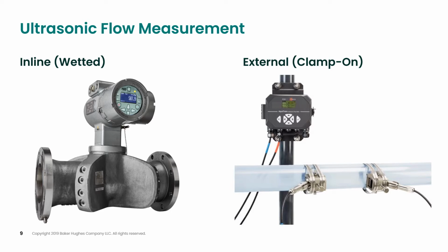With an external or clamp-on system, the transducers are installed on the outside of the pipe as shown in the picture on the right. Clamp-on meters are advantageous since they can be installed on the existing pipe without stopping your process. Clamp-on meters can also be used for troubleshooting with a portable battery-powered meter. Clamp-on meters are typically less expensive than inline meters since the meter body or spool piece is not required, especially for larger size pipes.